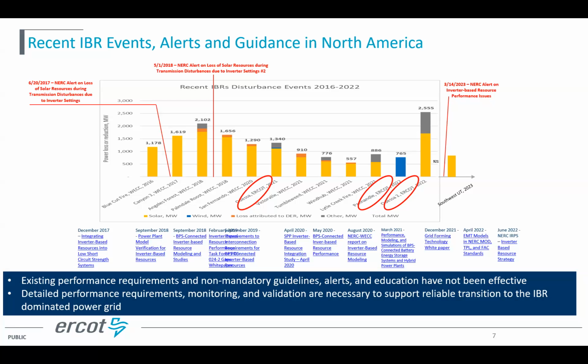Also, what is really the stability or reliability concern with high IBRs? In my opinion, it's really the IBR trip. If you look at this picture, it shows the recent IBR disturbance events, basically the IBR tripping events, since 2016, when we had the Blue Cut fire event. We had a lot of solar trip, and then similar events happened in ERCOT in 2021. In the Odessa event, we had a lot of solar unit trips.